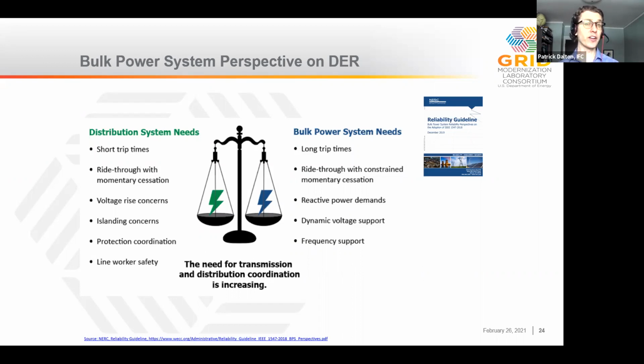The bulk system perspective is that we want DER to hang on as long as possible for most scenarios, continuing to support the system by producing power, which can act as a buffer when events happen. On the distribution side, there's still a general philosophy of trying to trip DER off quicker, to coordinate with distribution system protection in case a DER doesn't detect a system event. So there's tension here: distribution wants quicker tripping, concerned with voltage rise, while the bulk system wants it to hang on as long as possible because they want the support. There are discussions going on between distribution utilities and ISOs, RTOs, or transmission operators about how to strike that balance.